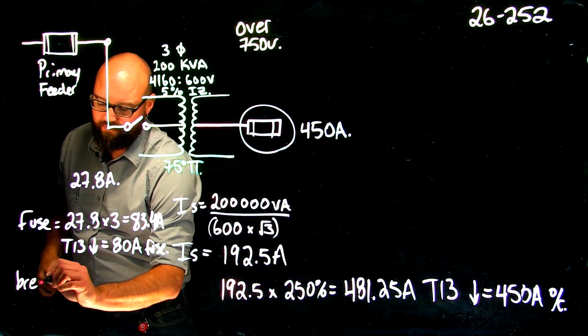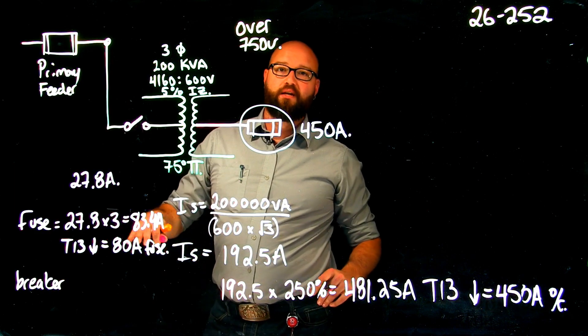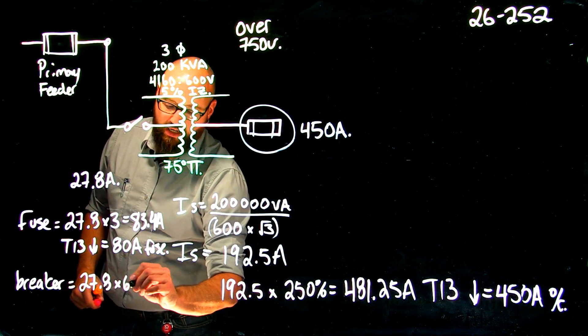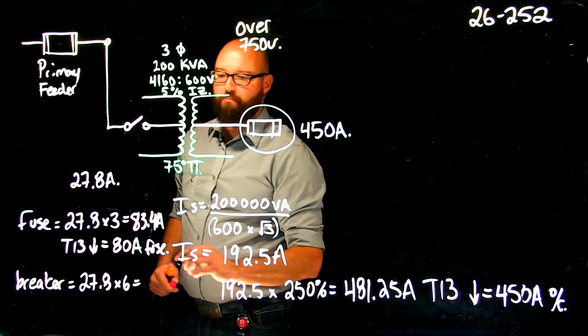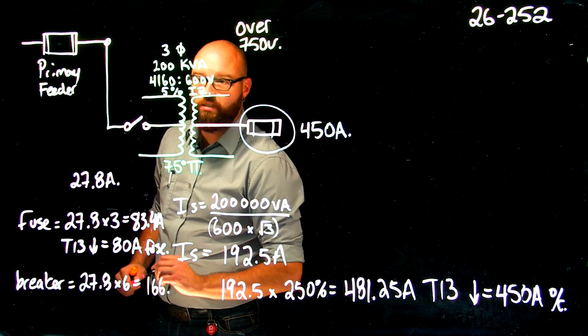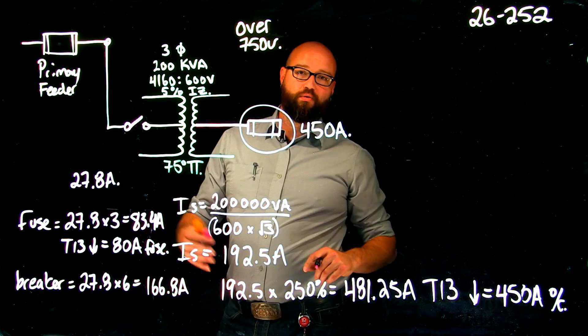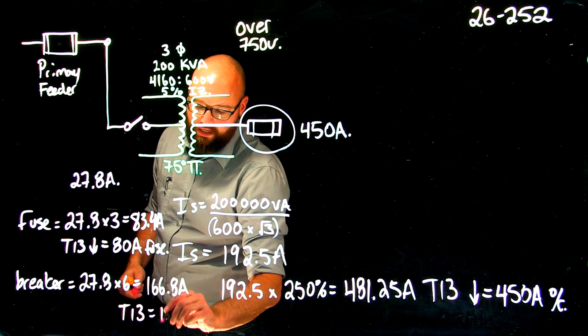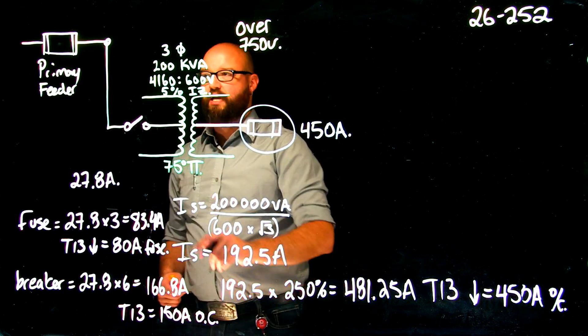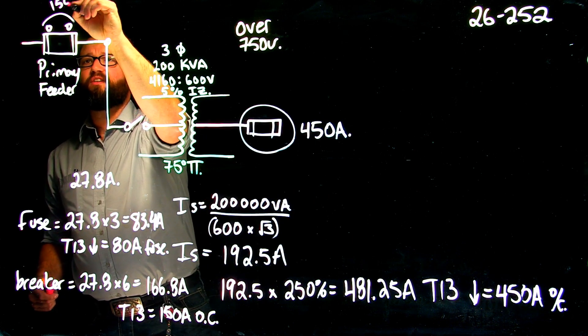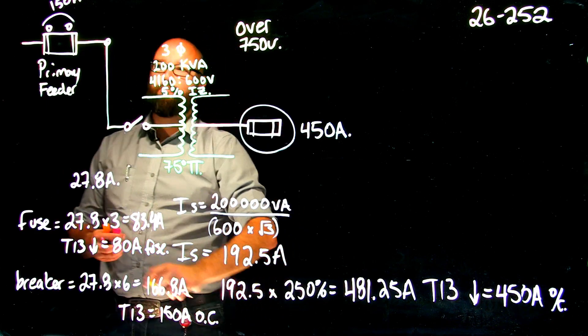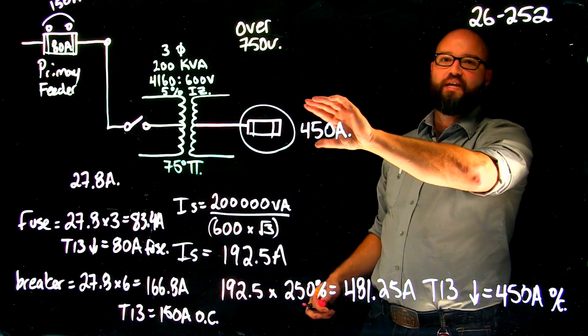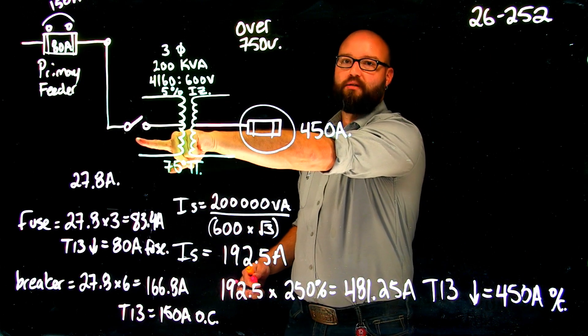If I was to go with a breaker, my multiplier according to table 50 is now 600% because I'm using a breaker. So 27.8 times six or 600% gives me a maximum rated value of 166.8 amps. The rules tell me that I shall not exceed this rated value or 600% of the rated value. So we go table 13 and we select a 150 amp overcurrent. In this case, if this was a breaker, it would be a 150 amp breaker. If it was a fuse, we would be looking at an 80 amp fuse.